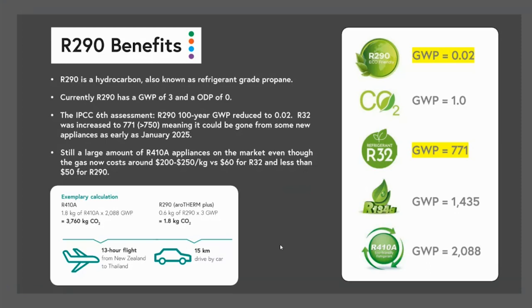There's now a 6th assessment, and it hasn't been ratified yet, but what it states is that R290 has a 100-year GWP of 0.02. So that makes R290, if this 6th assessment gets accepted, the lowest environmental impact of all refrigerants on the market. And that's quite a significant improvement and benefit for R290, even compared to the benchmark, which is CO2.